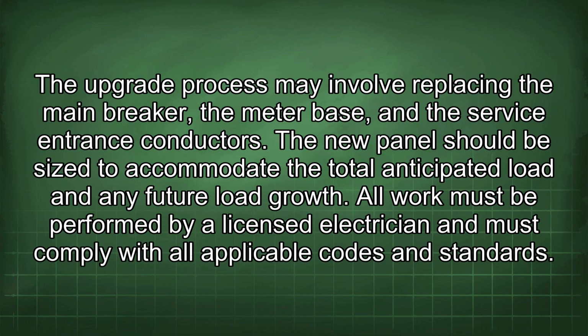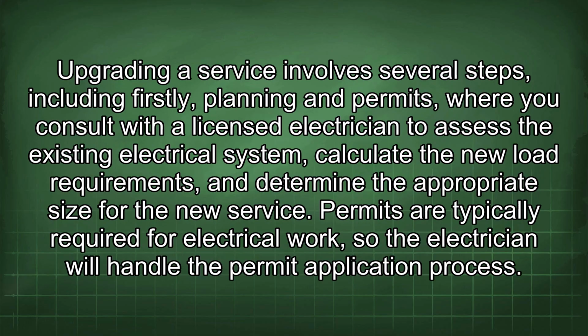The upgrade process may involve replacing the main breaker, the meter base, and the service entrance conductors. The new panel should be sized to accommodate the total anticipated load and any future load growth. All work must be performed by a licensed electrician and must comply with all applicable codes and standards. Upgrading a service involves several steps, including firstly, planning and permits, where you consult with a licensed electrician to assess the existing electrical system, calculate the new load requirements, and determine the appropriate size for the new service. Permits are typically required for electrical work, so the electrician will handle the permit application process.